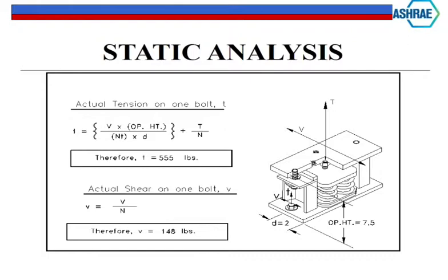They sort of look like this, where you figure out the actual tension on a bolt first, and then the actual shear, and then you do the same calculation twice over the vibration isolator to get down to figure out what your actual anchorage needs to be. If you're in a very low area, you might need a 12 or 13 millimeter bolt. If it happens to be in a very big area where there's going to be either a better chance of a bomb blast or a better chance of a seismic event, maybe this is a 16 millimeter bolt or a 20 millimeter bolt, something like that. But like I said, this is one of the areas that needs enforcement. This is where people go, I don't want to drill that big concrete anchor in, I'm going to put a small one in. And that's why you need to have some field enforcement to make sure you get the bolt that's required to do the job.